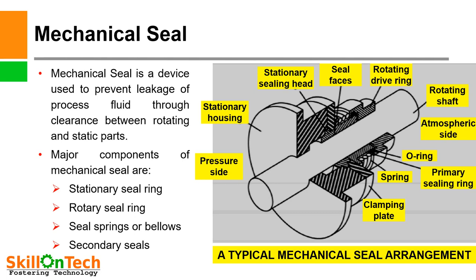A mechanical seal is a device used to prevent leakage of process fluid through clearances between rotating and static parts. The major components of mechanical seals are: stationary seal ring, rotary seal ring, seal spring or bellows, and secondary seals, which are O-rings and elastomers.